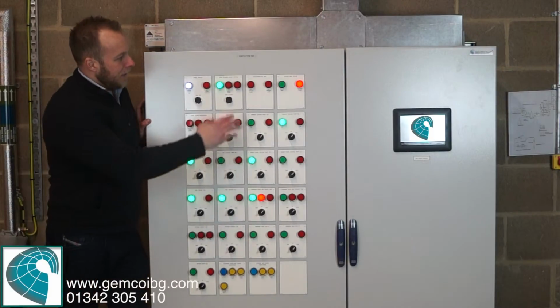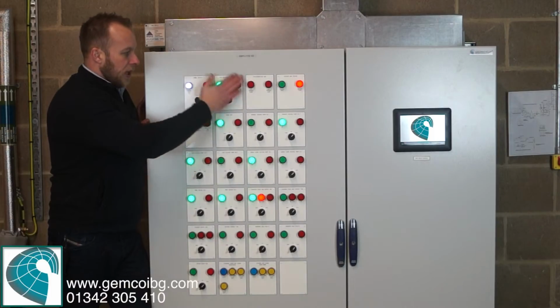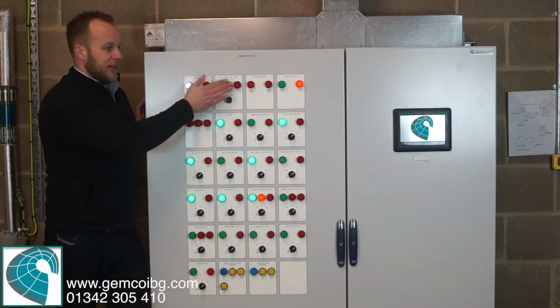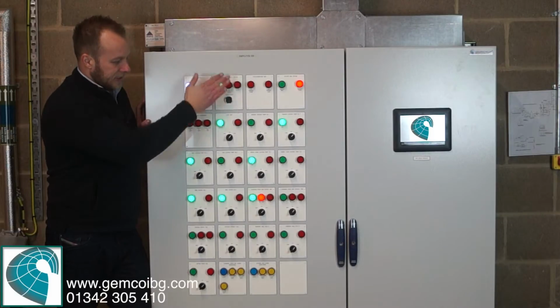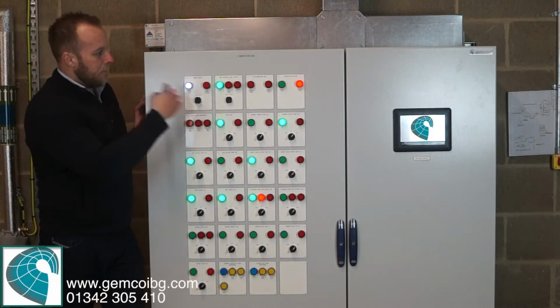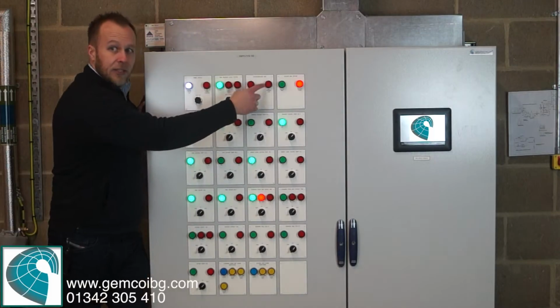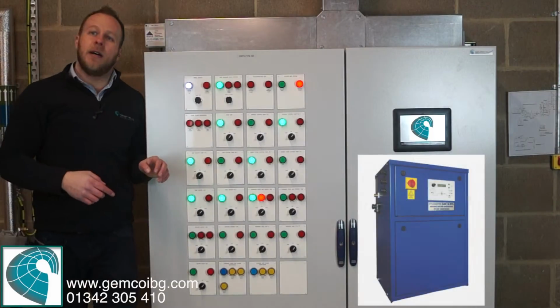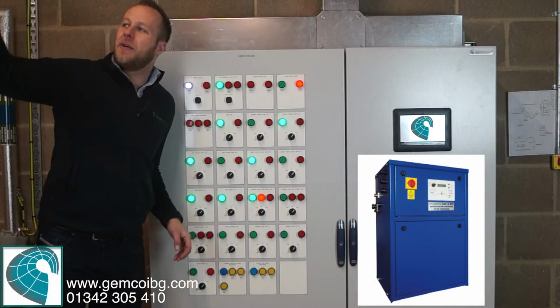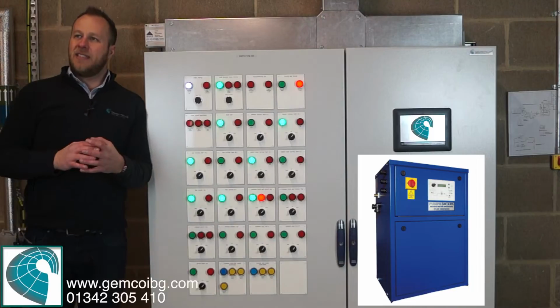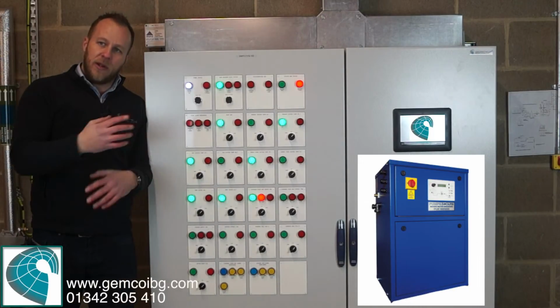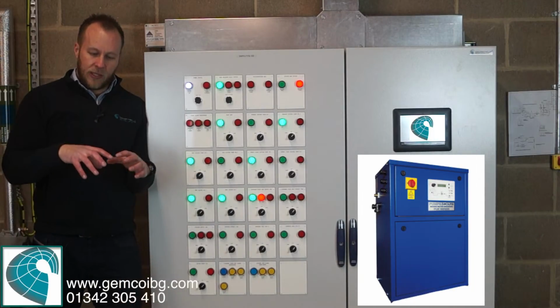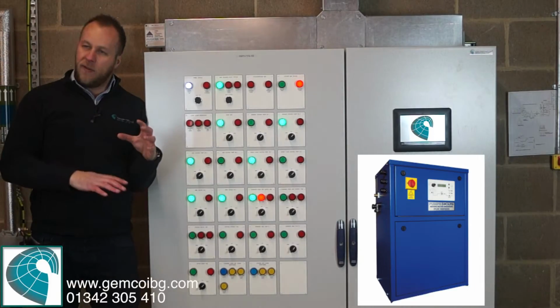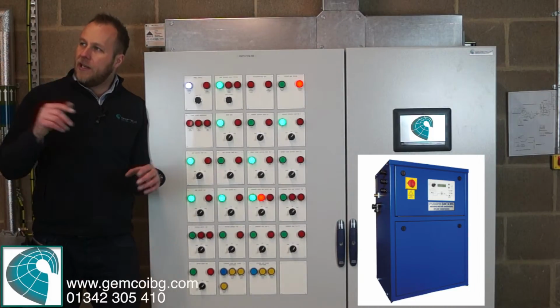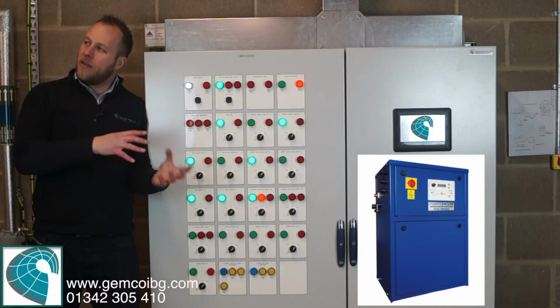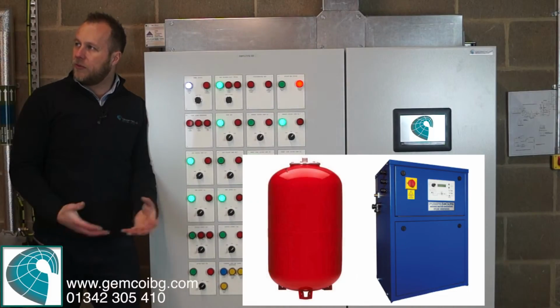All right. So they're your life safety systems, we call it life safety, but they're your hardwired safety systems for this control panel. On top of that, you've got a pressurization unit. There's a pressurization unit over there in that corner. And what that is, is a mechanical device. We don't control it from here, but we monitor it, and all it does is monitor the pressure in the system. And if it goes over pressure, it will take some pressure out of the system using a big balloon in a vessel next to it.